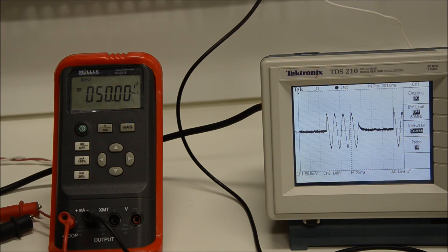So this delayed triggering technique is very useful. It allows us to burst fire into a transformer coupled load without spurious fuse blows, without that high current, and we get all the benefits of burst control which is very low harmonics, low noise.